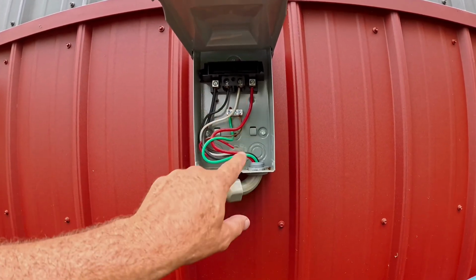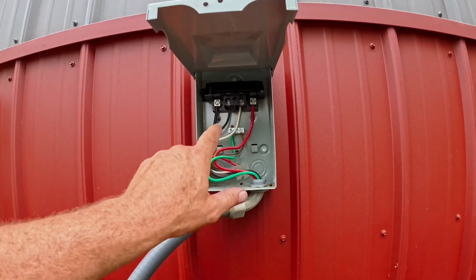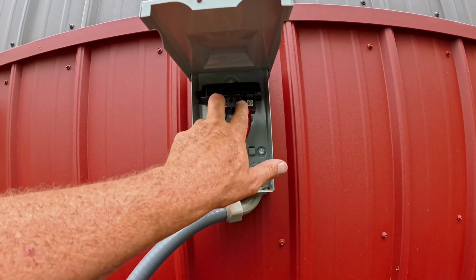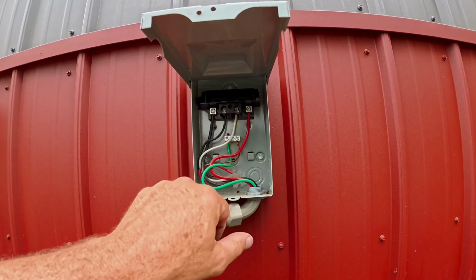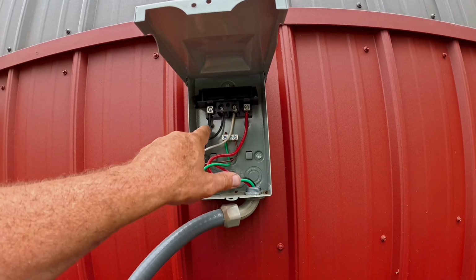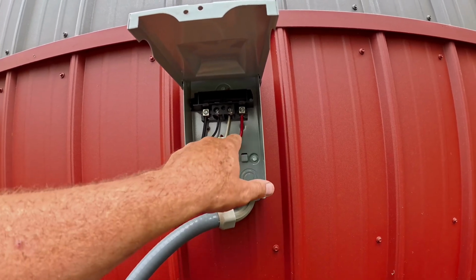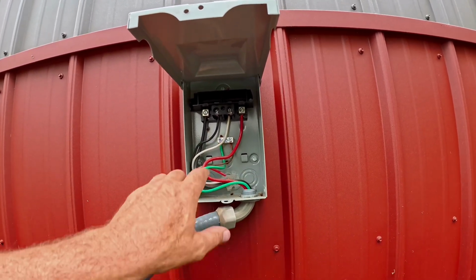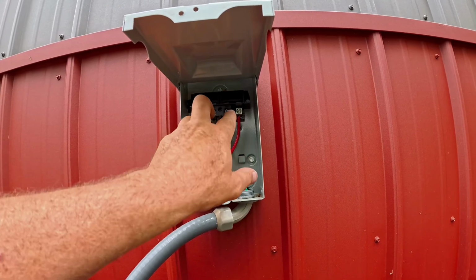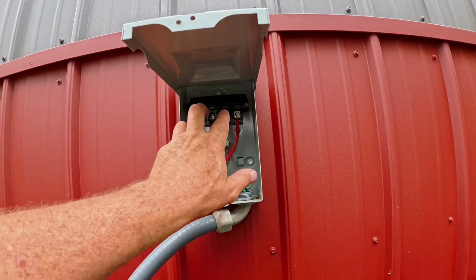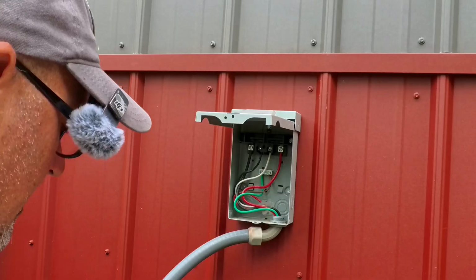So with the inside safety cover removed from my disconnect box, you can see the 4 wires up here. 2 wires are obviously the voltage coming from the fuse panel inside the house, and the other 2, which are the outer wires, are what goes to the AC unit. And right here it says line and line. So those are our lines coming from the fuse panel. So what we're going to do is check our voltage across those 2.